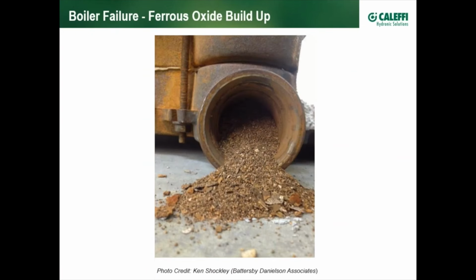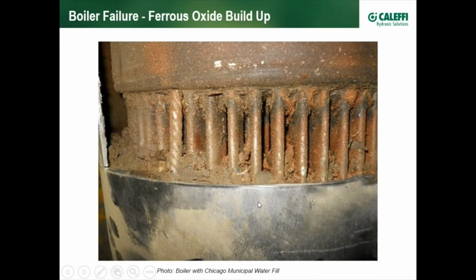More on that in just a second, but it's especially hard to eliminate because it's so small, oftentimes microscopic. So the result could be that debris can settle in places in the system, build up, and create failures such as this cast iron boiler that ended up leaking. Here we can see after the contractor basically replaced it, debris falling out, and from the red we can see some ferrous oxide, and we also can see some calcium or magnesium carbonate that has fallen off as well. So oftentimes not homogeneous debris is found inside systems that fail.